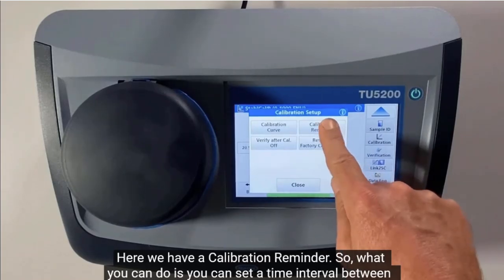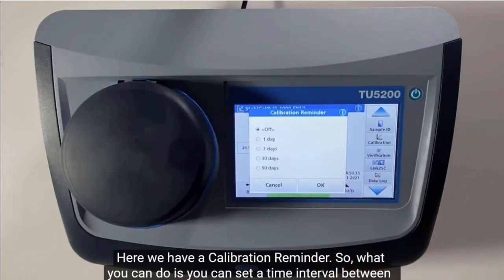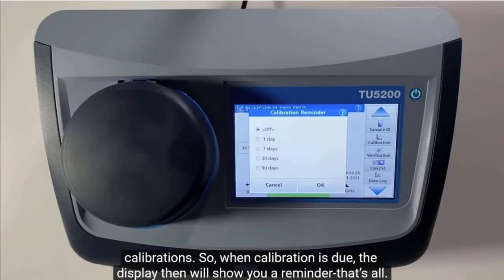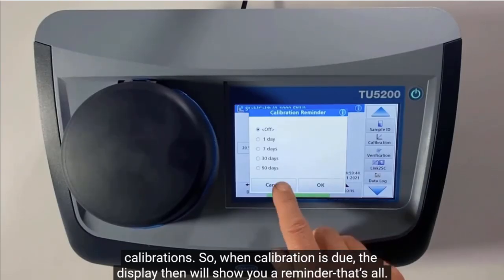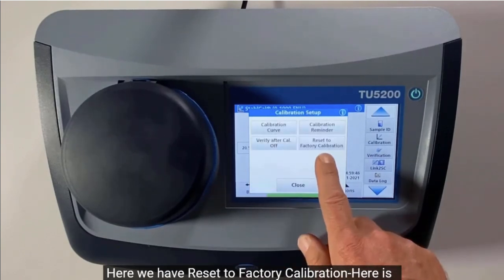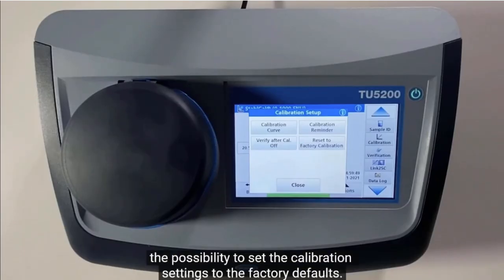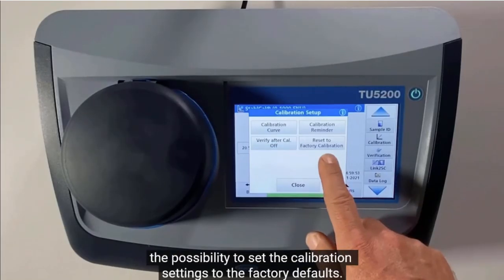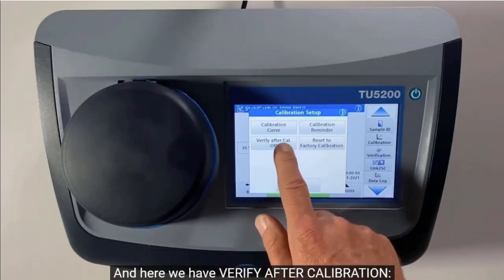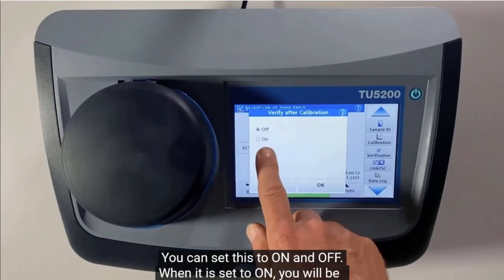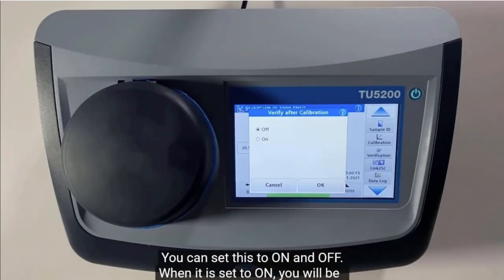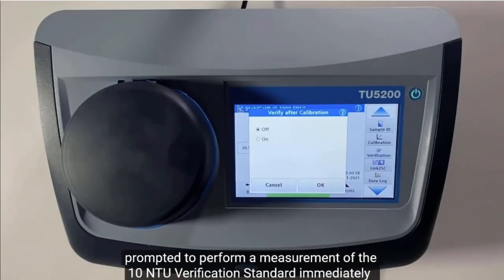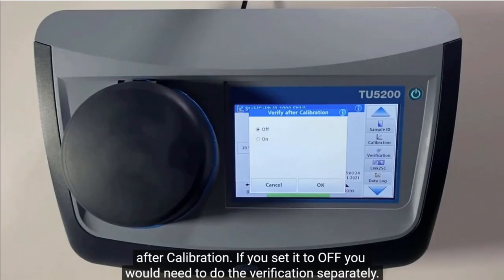Here we have a calibration reminder. You can set a time interval between calibrations, so when calibration is due, the display will show you a reminder, that's all. Here we have reset to factory calibration, where you can set the calibration settings to the factory default. And here we have verify after calibration. You can set this to on or off. When it is set to on, you will be prompted to perform a measurement of the 10 NTU verification standard immediately after calibration. If you set it to off, you would need to do a verification separately.